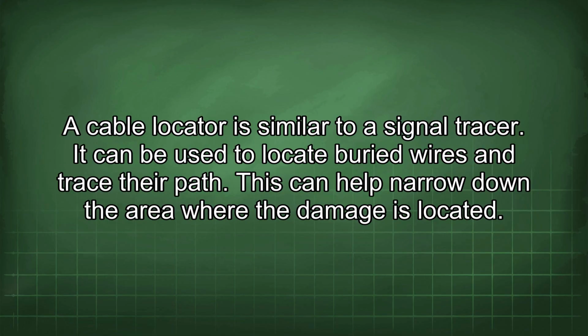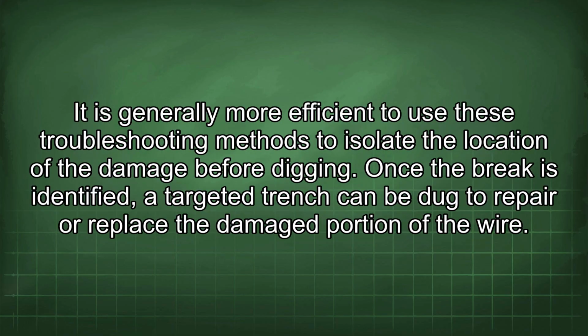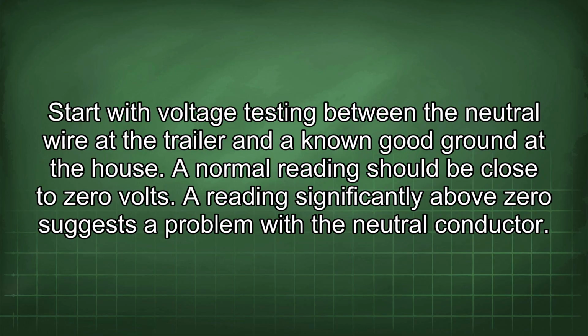A cable locator is similar to a signal tracer. It can be used to locate buried wires and trace their path. This can help narrow down the area where the damage is located. It is generally more efficient to use these troubleshooting methods to isolate the location of the damage before digging. Once the break is identified, a targeted trench can be dug to repair or replace the damaged portion of the wire.